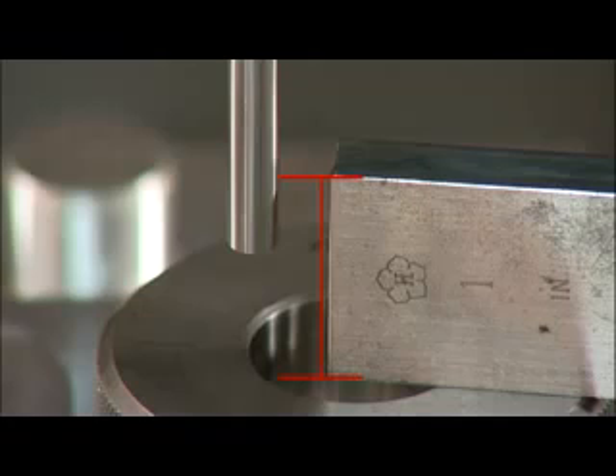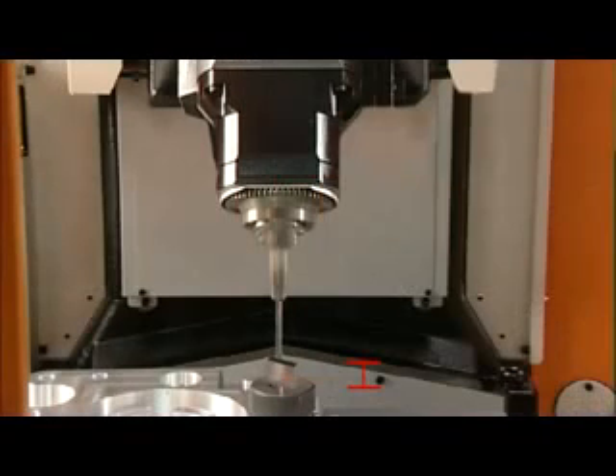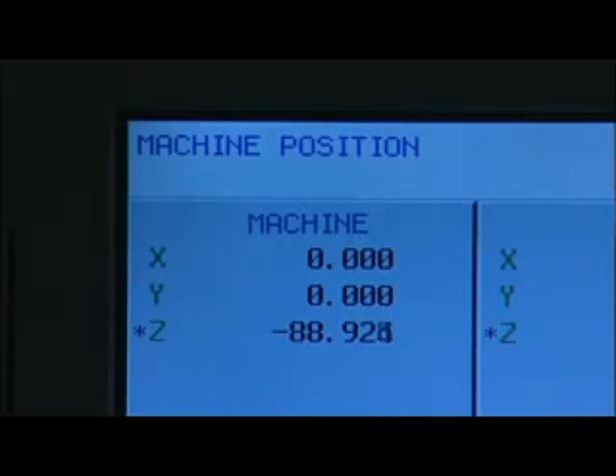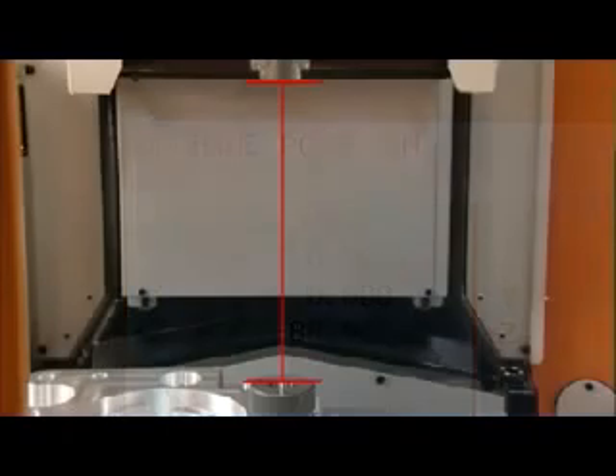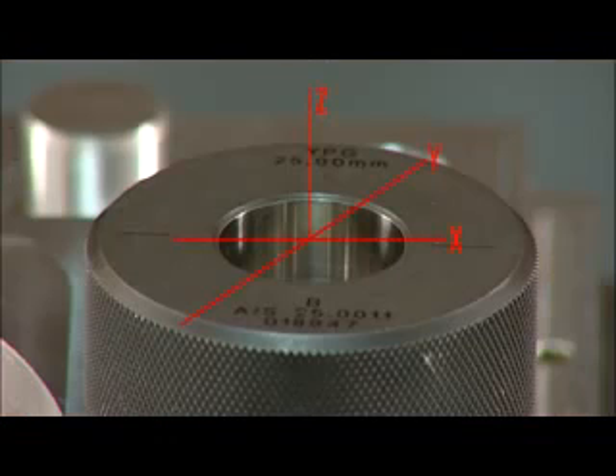The thickness of the slip gauge and the length of the comparator or tool of known length are added to the position recorded from the machine Z encoder. This gives the relative surface position of the ring gauge to the spindle nose or machine datum. Now the user has the precise X, Y bore position and Z surface height of the ring gauge to the machine datum.